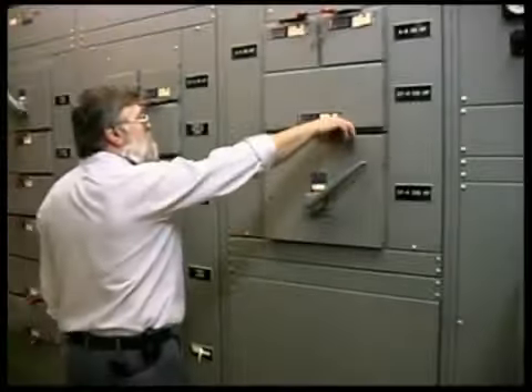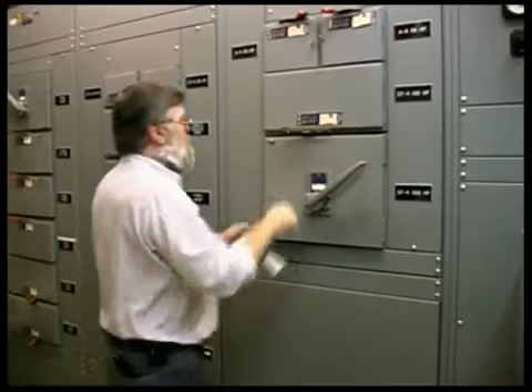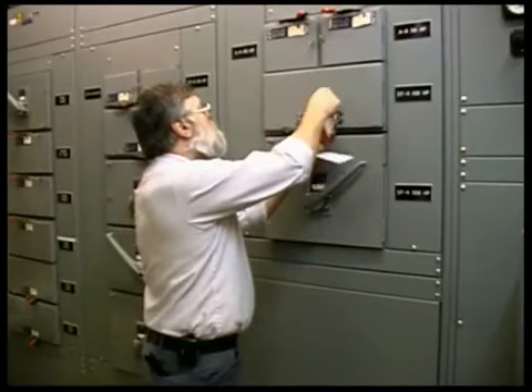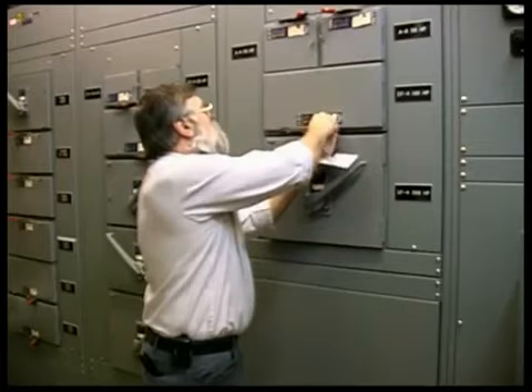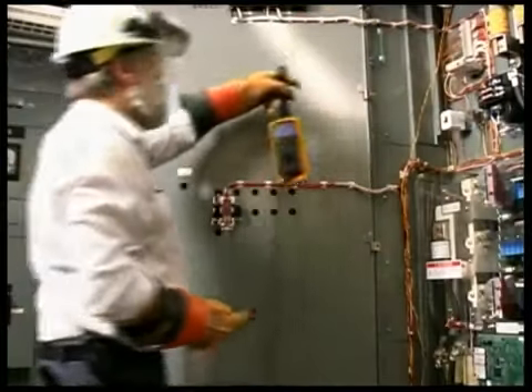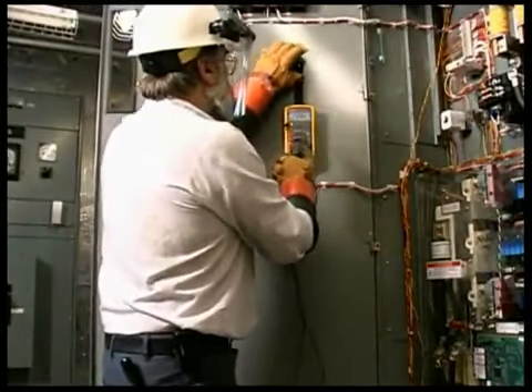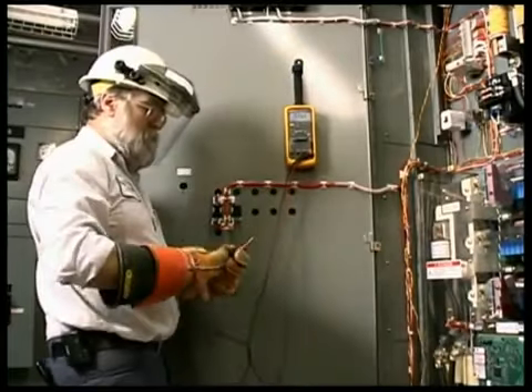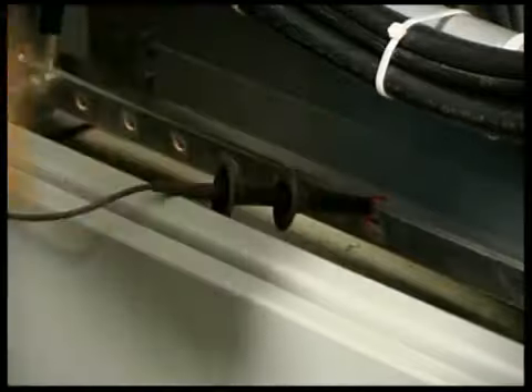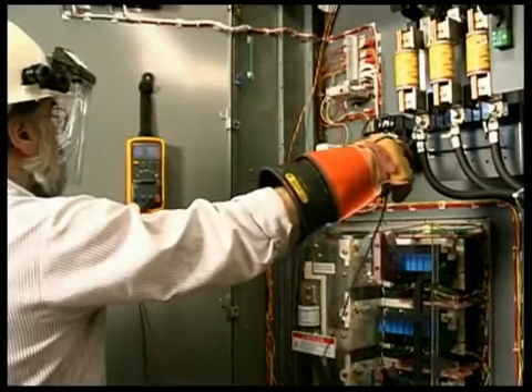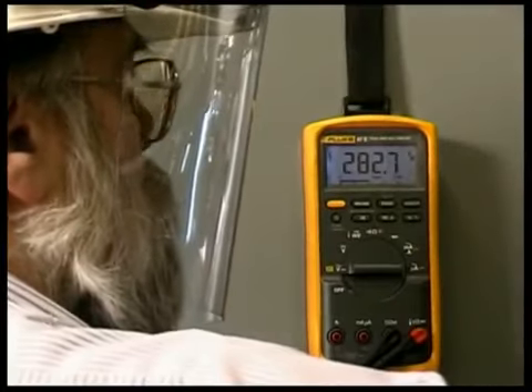Whenever possible, work on de-energized circuits, and always follow proper lockout-tagout procedures. When taking single-phase measurements, always connect the grounded lead first, the hot lead second. After taking your reading, disconnect the hot lead first, the grounded lead second.